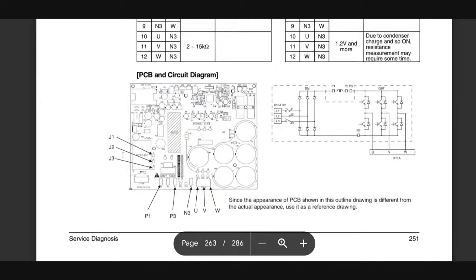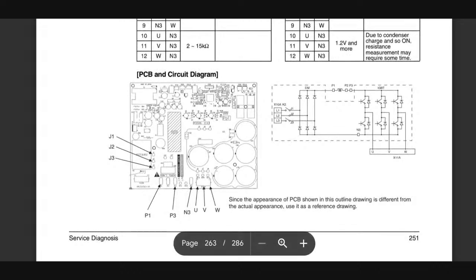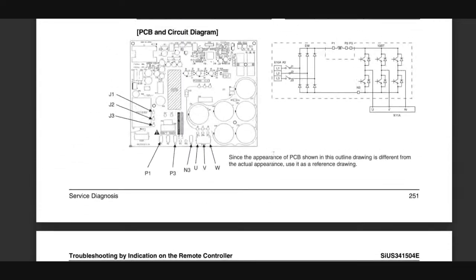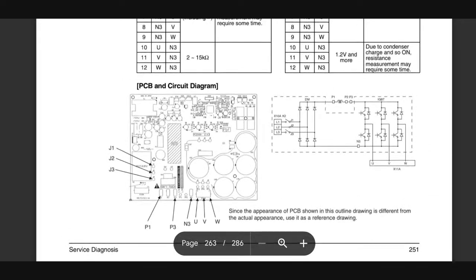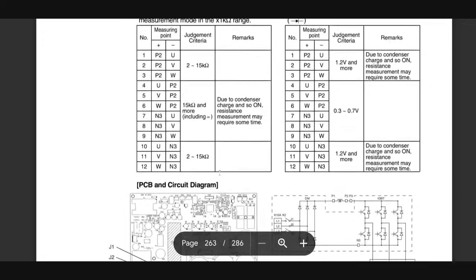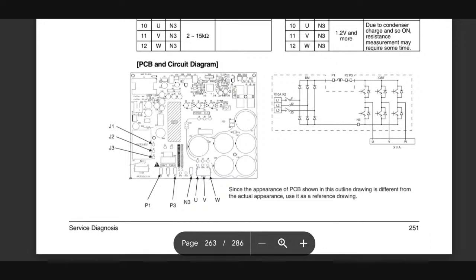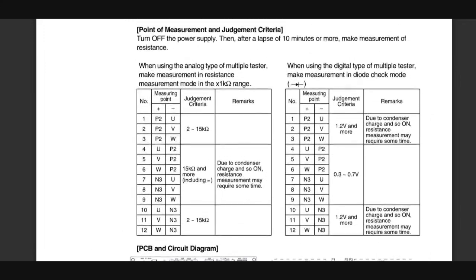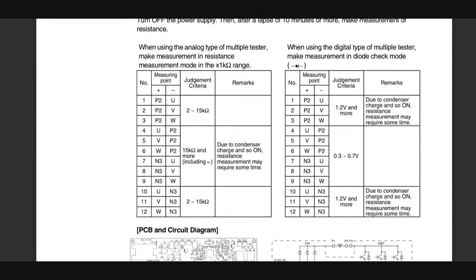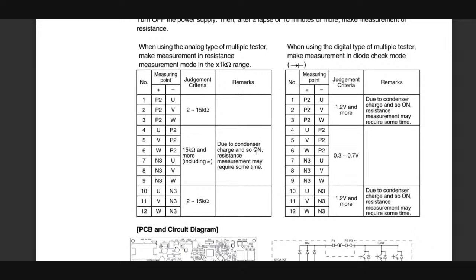So between P2, is that what I said? P2 and W. Yeah, right here. So here's P2 on this middle terminal. We'd read between this terminal leg, this is with everything disconnected, and W, or U. There we go. So you would go through this process, this entire check. If anything failed or was outside of tolerance, it's going to lead to an automatic failure. Now here's that diode symbol I was telling you about earlier. The diagram to the left is specifically doing an ohms test.